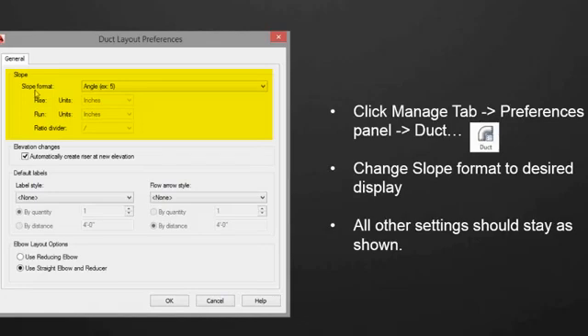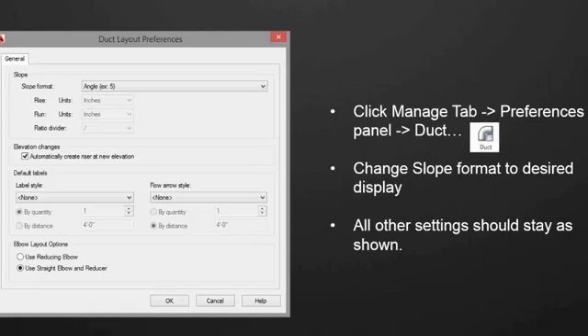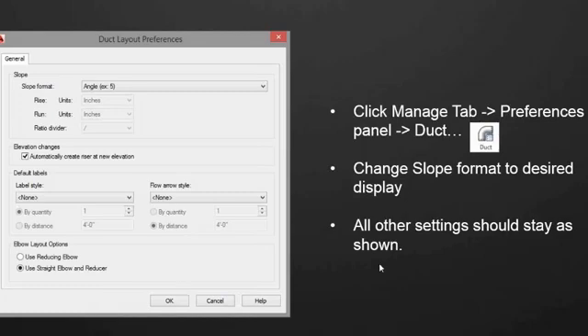And then finally up here at the top is the slope format. This might be the one that most people will change the most often. Different shops might display their slopes differently, but there are several different options there. Angle is a good one to use. Most people would probably use rise over run. That's what I'm most accustomed to in the piping world. So one-eighth inch slope would be rise or drop an eighth of an inch over one foot. So this is something you should have set up. It's simple to do, it takes a couple seconds. You do it in your template.